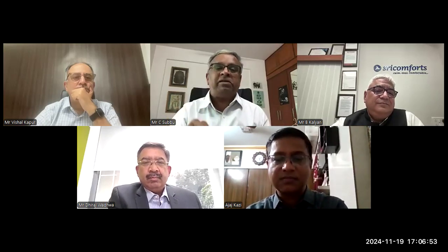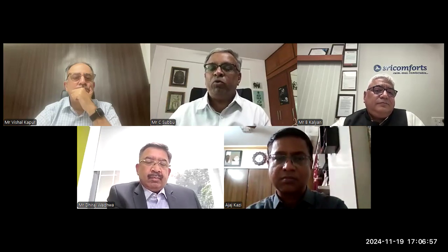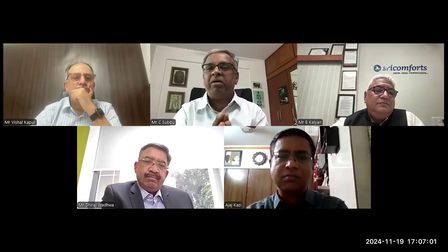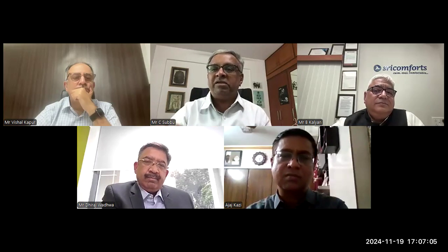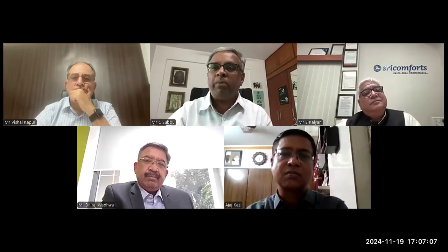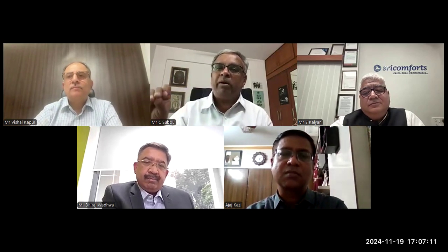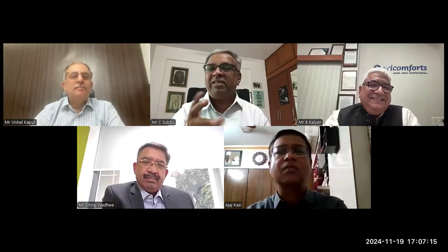See, today what happens is, somebody supplies the chiller, somebody supplies the AHU, somebody supplies the BMS. Who is tying them together? What makes it work together? Somebody has to tie it up. Now, it's an integrated system. As Dhiraj said, integrated system efficiency, system kilowatt per ton, is what we want. Now, if everybody handles one equipment each, who is going to do the system kilowatt per ton? What am I going to get? I think that is where the problem is.